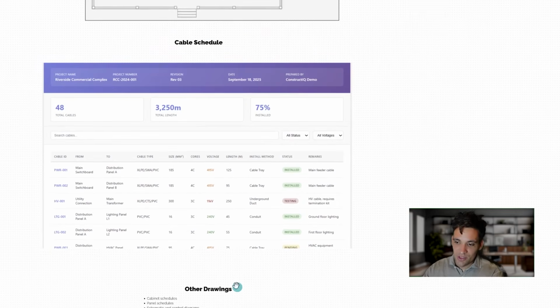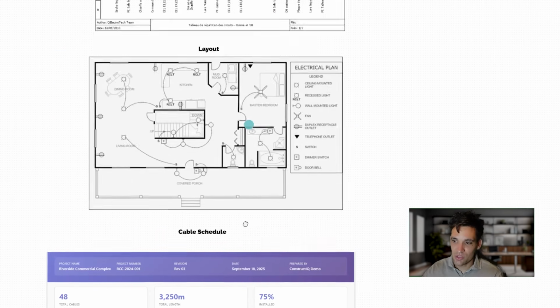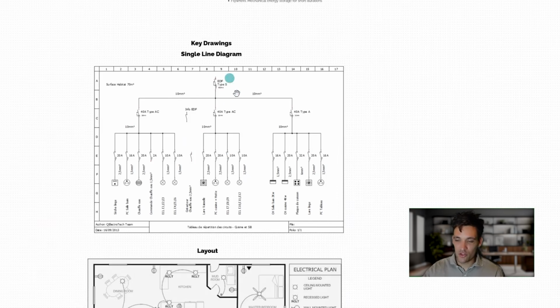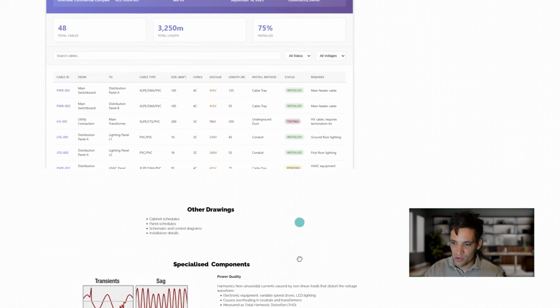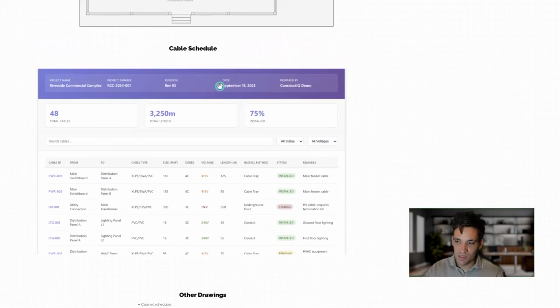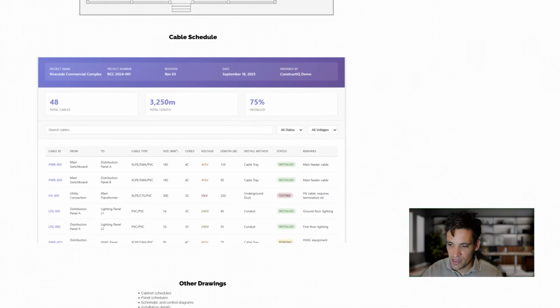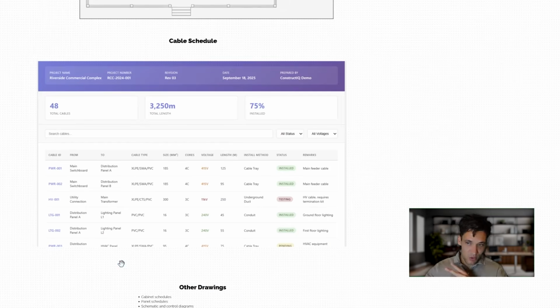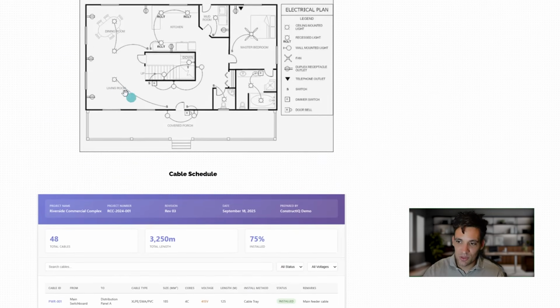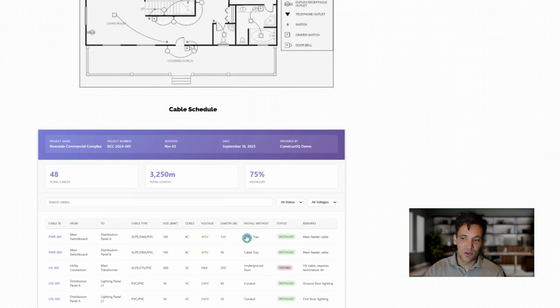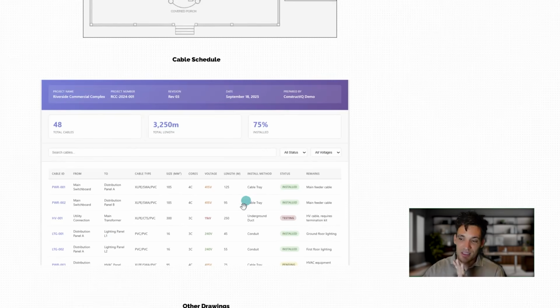You might also get other drawings, again depending on the project and its size and complexity. You might get individual cabinet schedules and panel schedules, so an individual drawing for each of these distribution boards and the main switchboard. You might also get control panel schedules if there's control logic and control boxes going in. You might get schematic and control diagrams, and additional typicals and installation details. Like there might be a typical for this type of light fitting, what it's meant to look like, or this type of light fitting that's mounted on the wall. So those are just typical drawings that you see on any electrical construction project.